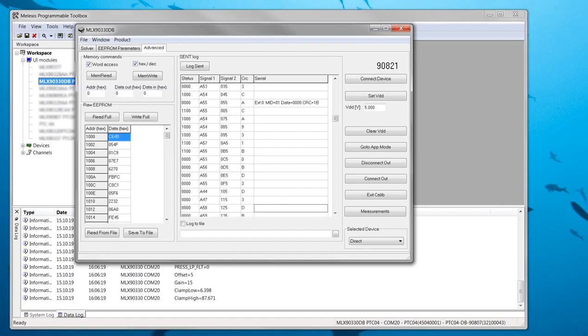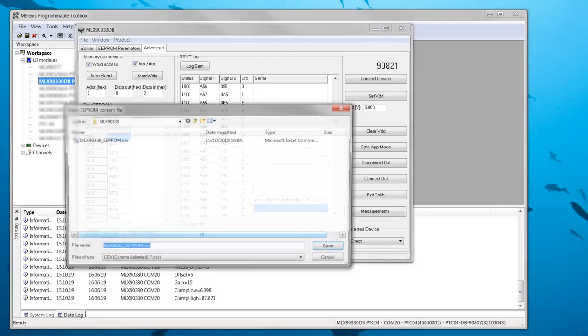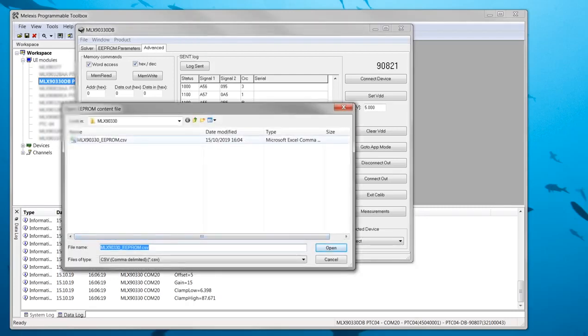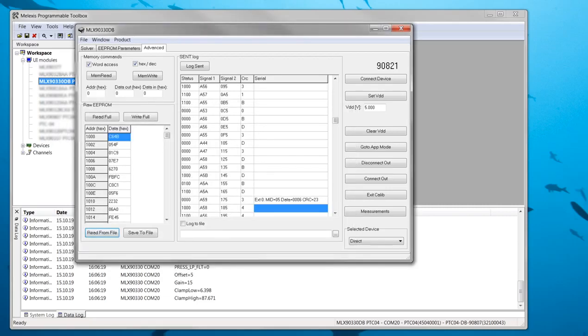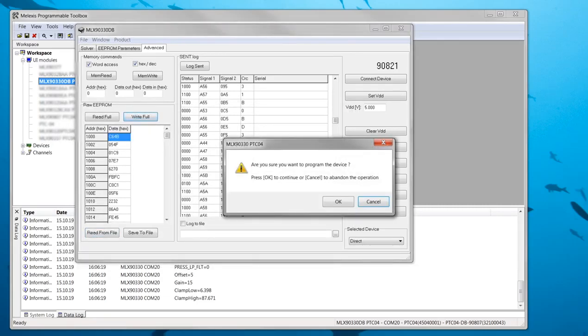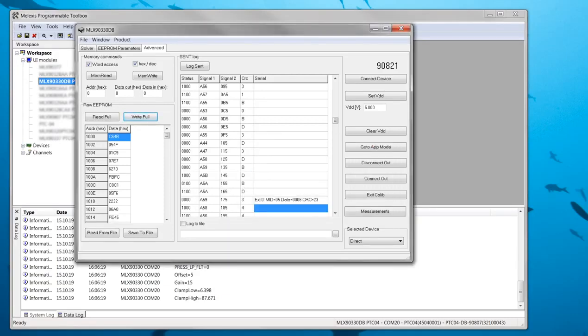To end the demo, I will recover the original state from the E²ROM we saved earlier to a file. First press Read from File to display the E²ROM content in the raw E²ROM table. Then press Write Full to program the device. Like the Program E²ROM button, Write Full generates a pop-up to confirm that you want to override the E²ROM content. The device is now back as it was before I changed the repetition of the diagnostic information.